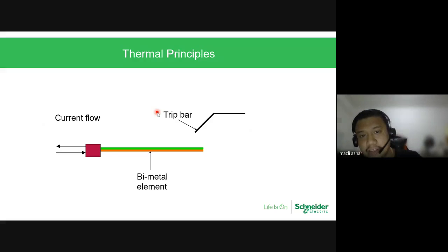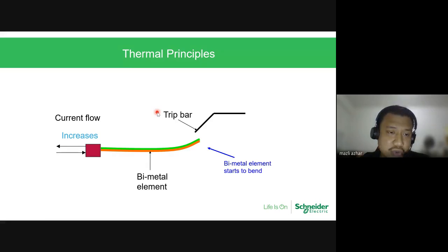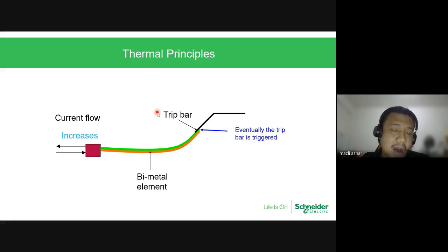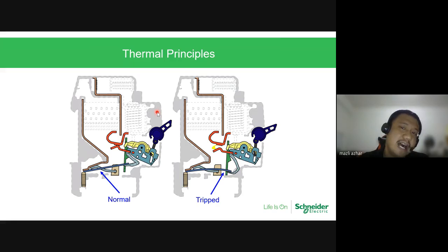So, the thermal principle. If you recall in my previous slide, in the architecture of a breaker, there is a bimetal element. This bimetal element is two metals with different rates of temperature rise, whereby at normal current flow, the bimetal will not have any issue. But when there is an overload, the bimetal will start to bend, but it still does not reach the trip bar, because it has not reached the level of tripping. But when the current flow increases, it will touch the trip bar, and then it will open the circuit. So this is how it looks in a normal condition. In a trip condition, you can see the bimetal has bent and touched the trip bar to open the circuit, whereby the power contact will open and the arc created will be extinguished at the arc chamber here, or arc chute.